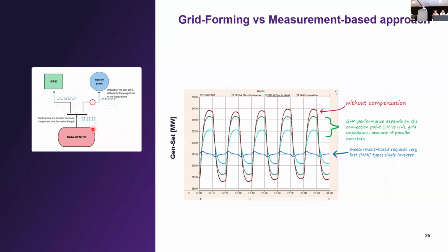The reason for this is that grid forming itself does not directly react to the load change. It reacts to the phase angle and the frequency change which is caused by the load change, and it reacts proportionally to the impedance, right? So it's quite effective if it's connected very, very close to the source, so on a low voltage side at a rack level. Once you move farther away behind the medium voltage transformer, the efficiency will be way less. And once you move to the high voltage side at the POI, grid forming will not provide that much of a compensation degree.